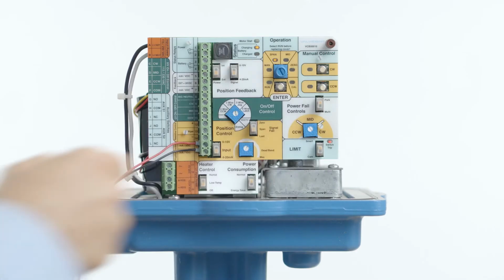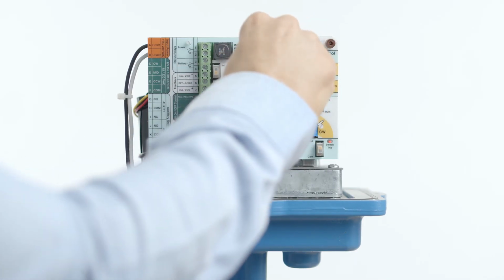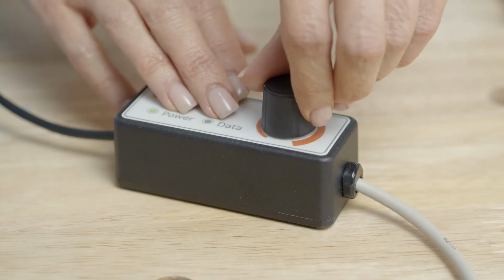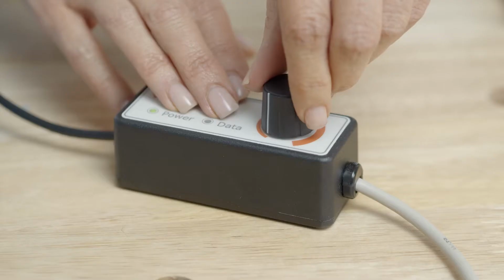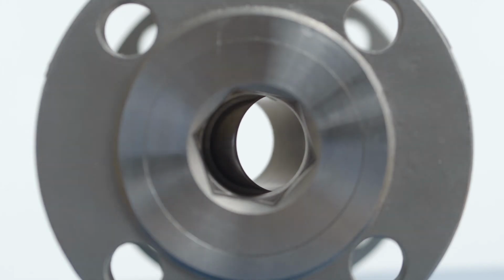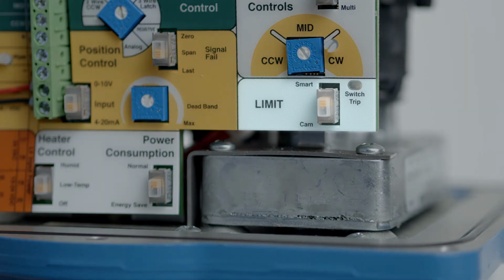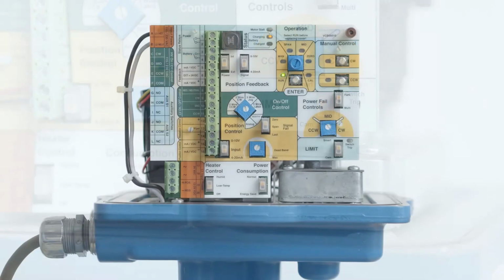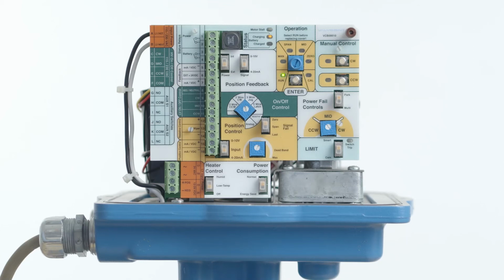To verify end of travel settings, turn the mode selector dial to Run. Apply various control signals to verify operation. Verify the switch trip LED is not illuminated at either the 0 or span positions. If it is, back the respective end of travel cam off the respective limit switch.